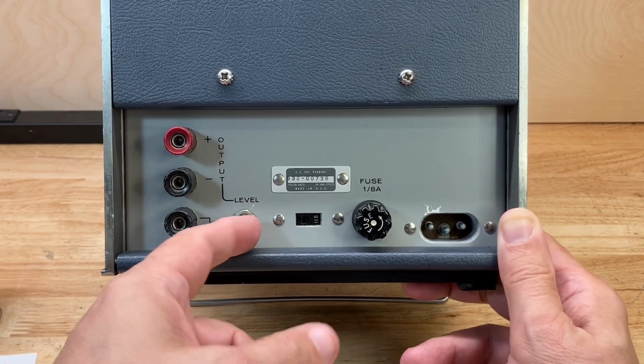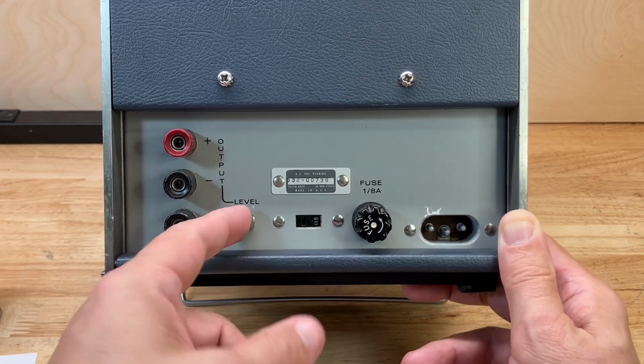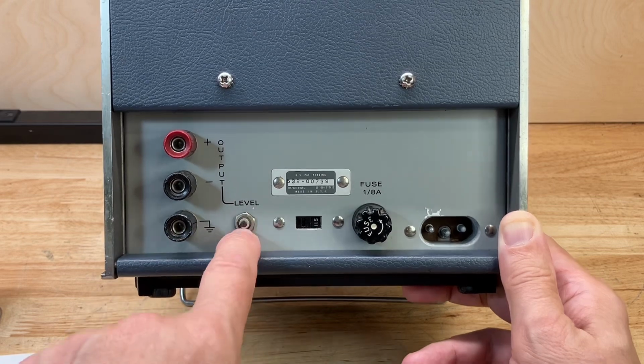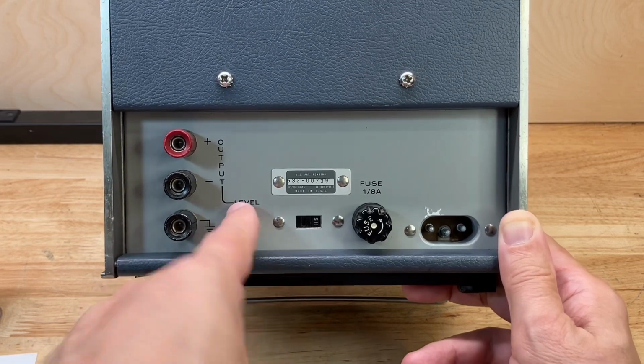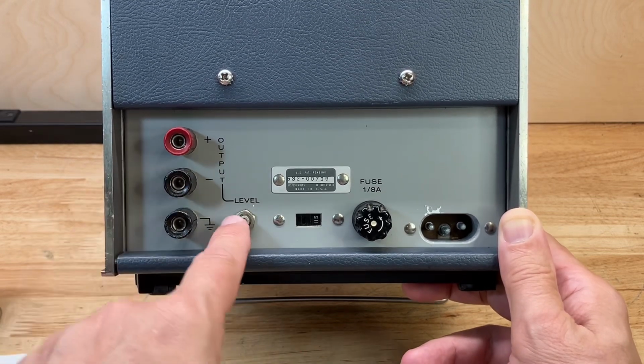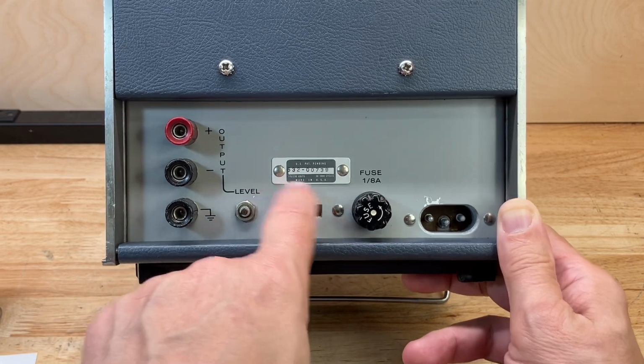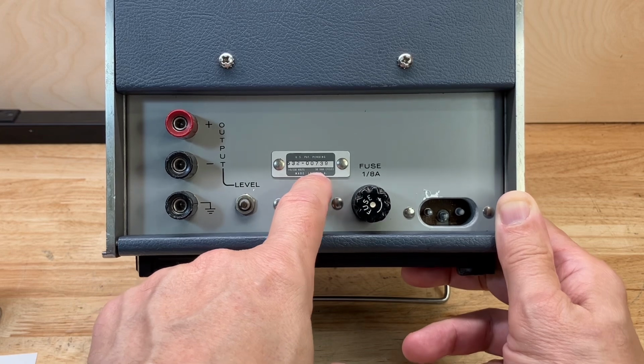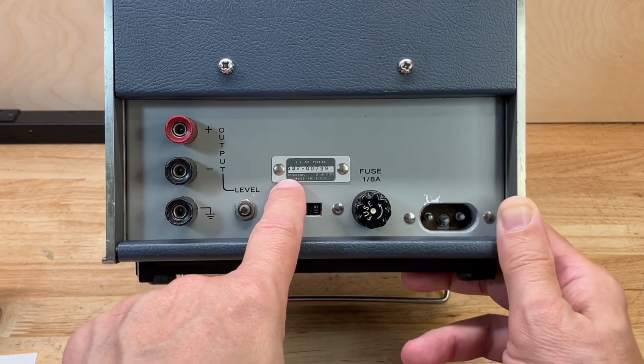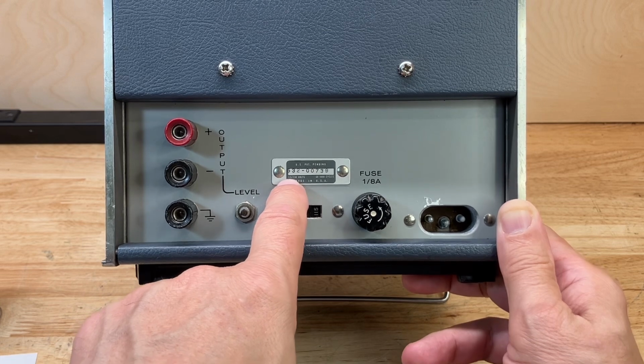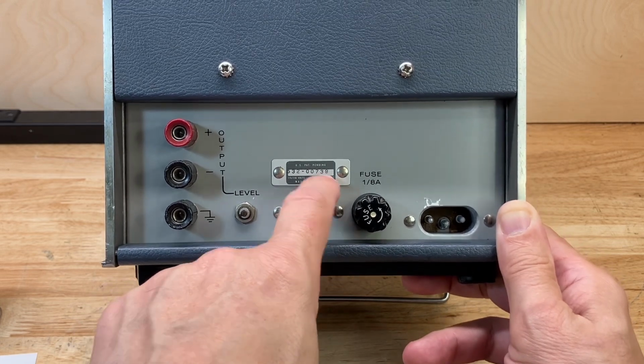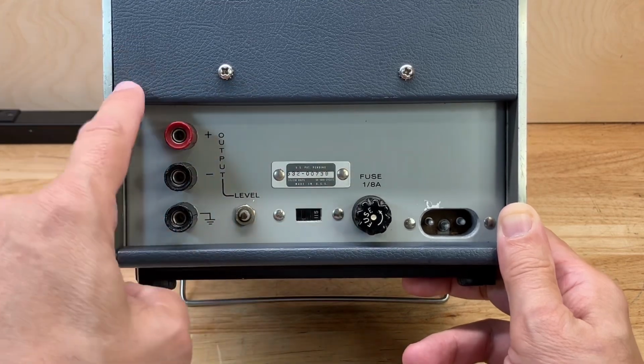And there's also an adjustment level control you can adjust with the screwdriver to calibrate that output level or adjust it. Serial number plate: 532-00739. That implies that this instrument was made in around 1965, and its number 739 is one of the first ones HP ever made. This is a very old instrument.